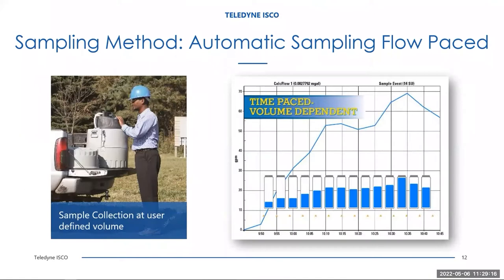This is an example of a time-paced program where we are adjusting the volume delivered to the bottle based upon the flow rate occurring at the moment the sample was collected. So when the flow is at lower levels, the amount of volume in the bottle is less; when the flow is at a greater amount, the bottle is fuller. The difficulty with this is if you do not know what the flow is going to be at that site, it could be very easy to under- or over-pace that sampler. If you design a flow program based for a lower flow than what actually occurs, all the bottles may be near full rather than being truly flow-weighted over that sampling interval.